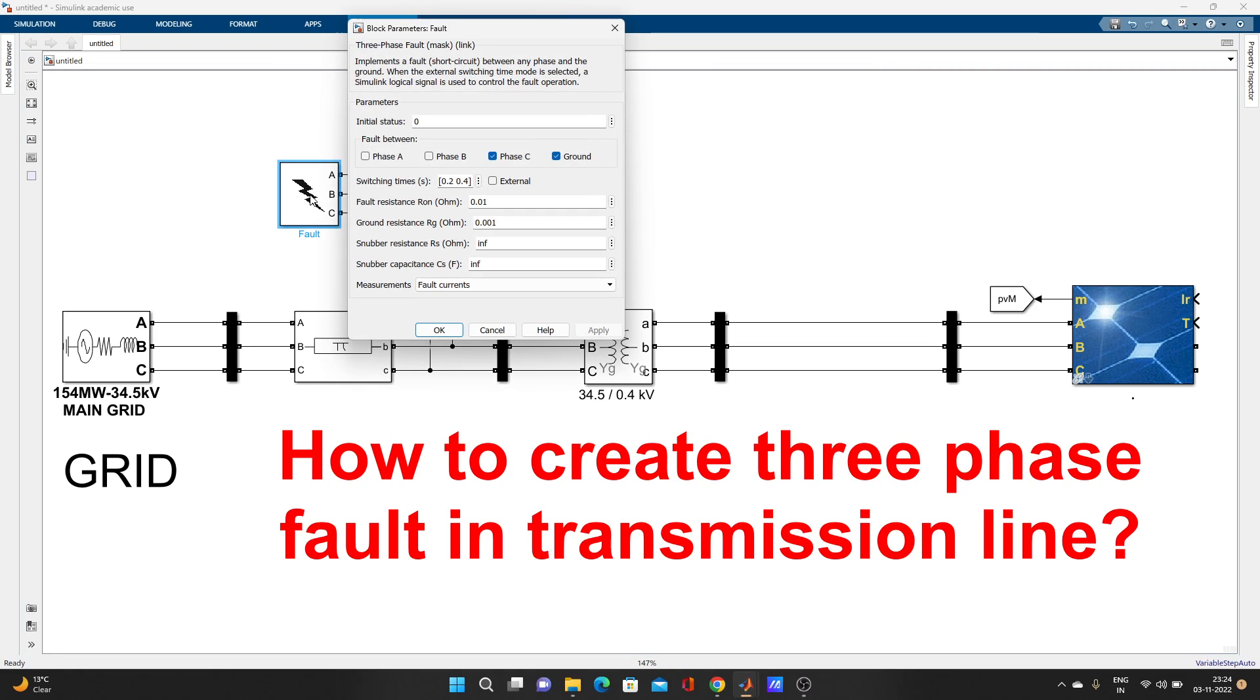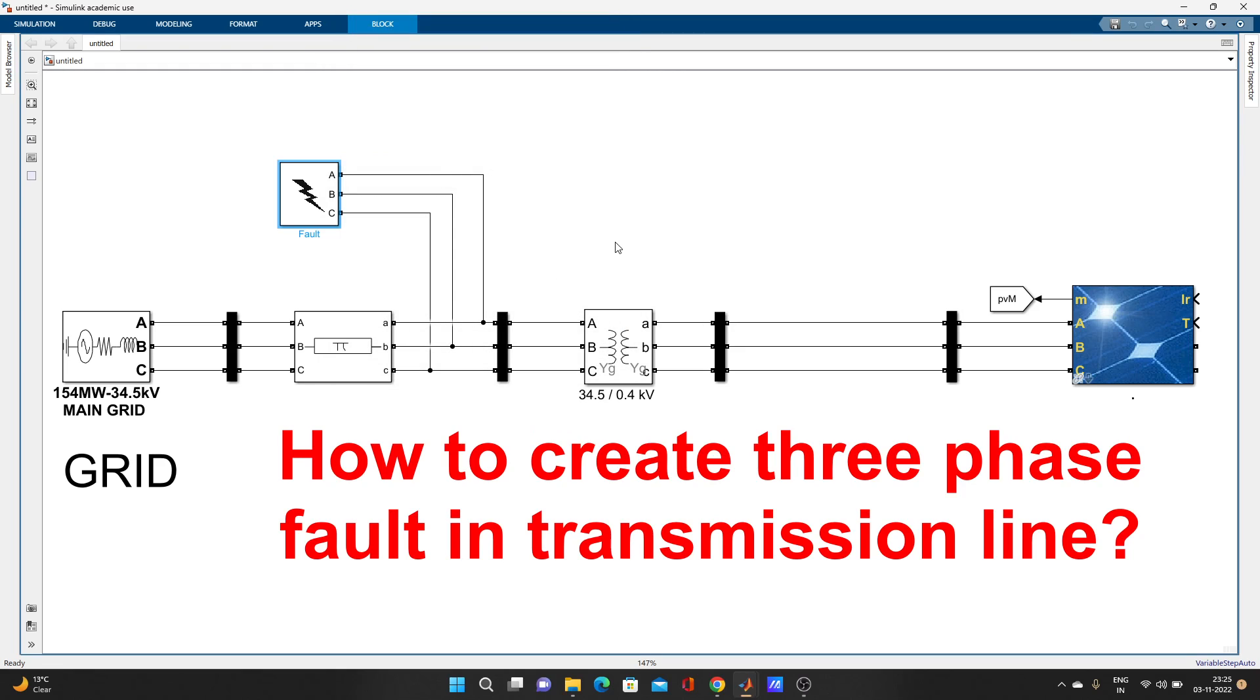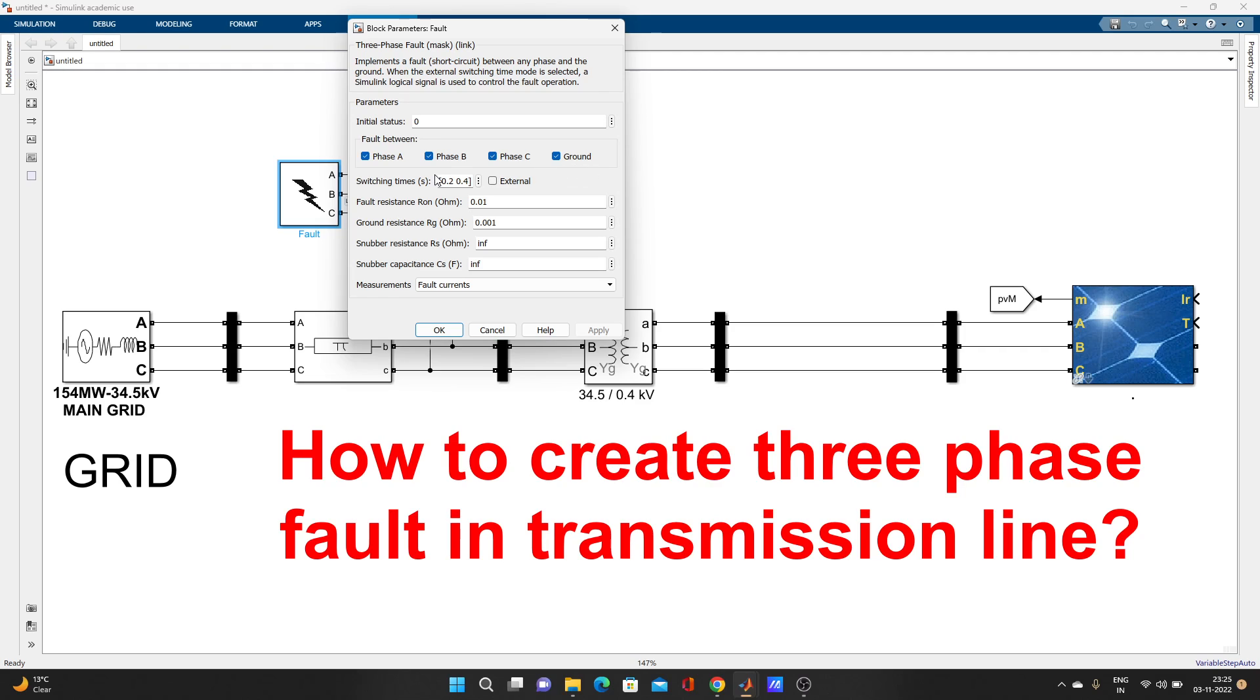And just double click here. In three-phase fault, you can create so many types of fault: phase A to phase B means line to line fault, line to ground fault, double line to ground fault. You just need to click on it, then it will be the fault. If you click ABCG, suppose here already ABCG is clicked, so that means this is a three-phase fault. The fault type is ABCG fault, which means three line to ground fault.